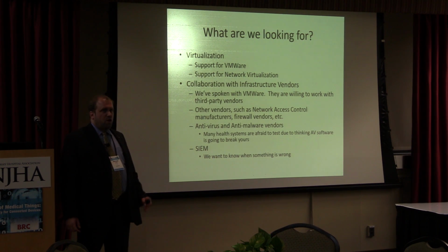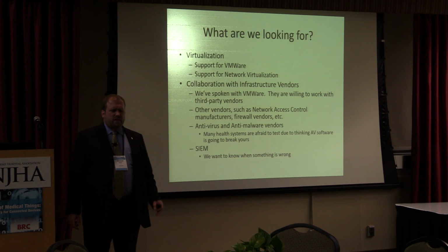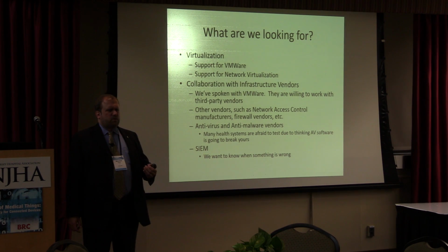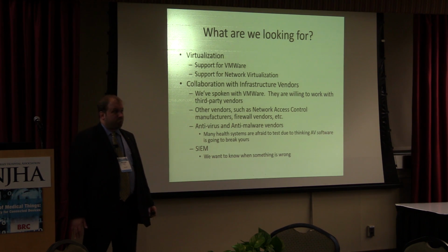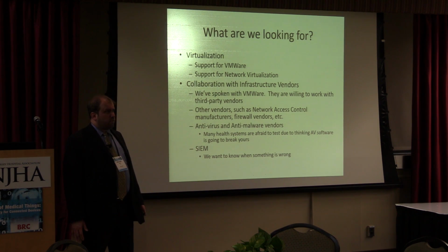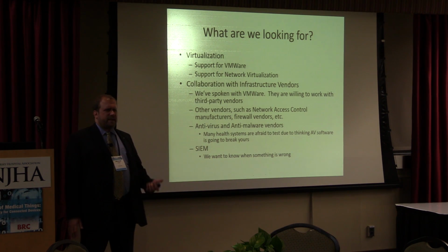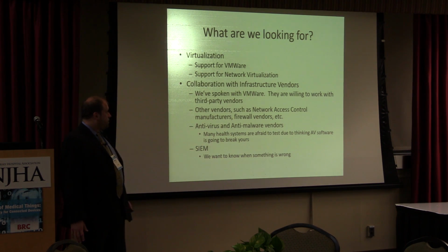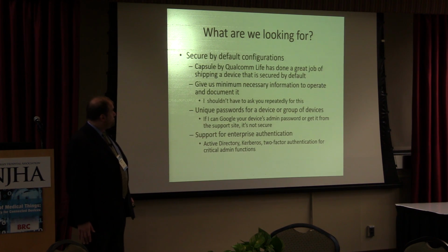Antivirus and anti-malware vendors. What we have actually noticed is that a lot of medical devices out there, we're talking lab testing equipment I've personally seen, other sorts of equipment, even radiology. Everyone's scared to put antivirus or anti-malware software on their devices because they think it's going to break. I can tell you there's been a few vendors that have warmed up to it, but this is still a problem. And a lot of health systems are afraid to test antivirus because they're afraid antivirus is going to break the device. So we want to make sure that you're working with antivirus. And SIEM, we want to know when something is wrong and what to look for. It's about the data.